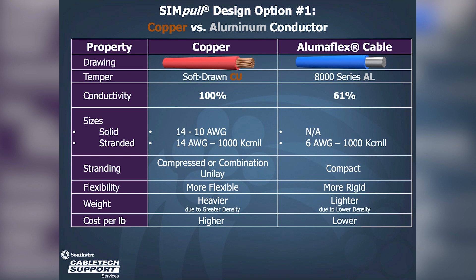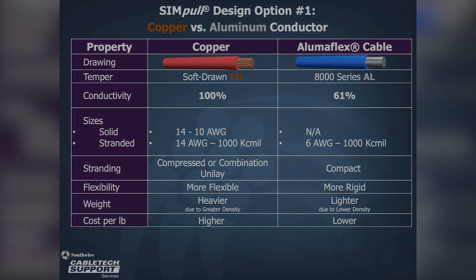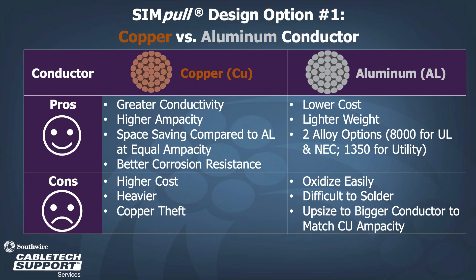Aluminum offers a lighter weight and lower cost product compared to copper. Looking at the pros and cons of each conductor material, copper conductors offer greater conductivity, higher ampacity, space savings compared to aluminum conductors of equal ampacity, and better corrosion resistance. The cons are higher cost, heavier product, and copper theft.